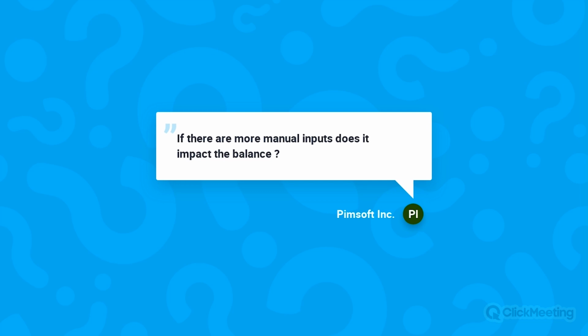Coming back to the earlier question, validation is even more important in this case, because you have to ensure that you don't receive any bad data. And if you receive bad data—for example, some data not coming from the historian—you should be able to supply something in its place. So there is a set of techniques to make sure that the equipment balance is always solvable without manual intervention.